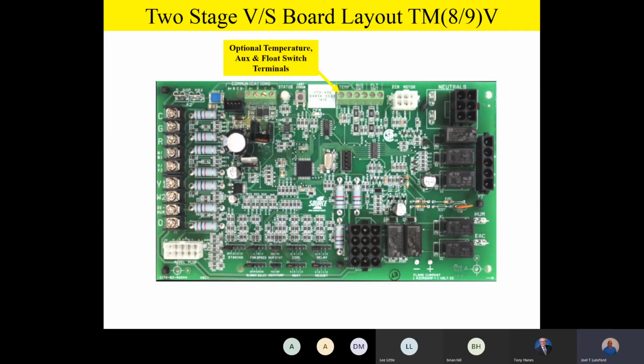Now, if you decide to go communicating with this control board or with this furnace, if you decide to go 4-wire communicating, you get some optional temperature, auxiliary, and float switch terminals as well. So you can hook up some accessory devices if you have them set up for communicating. You'll have a little visual cue as well. You'll notice the communicating terminals are little green screw terminals. So keep that in the back of your brain. If you're going to go communicating, you have available some accessory temperature, auxiliary, and float switch terminals. Right next to those terminals, you have an ECM motor plug.